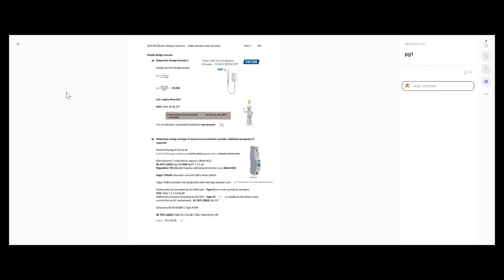So we're going to go with a 50 amp Type B for the MCB side of the RCBO, and a Type AC for the RCD part — 30 milliamps. We'll select a BS EN 61009-1, which is the product standard for an RCBO, Type B 50 amp. When we look back at the formula, I need a protective device equal to or greater than my design current. I couldn't choose a 45 amp RCBO because it's less than the design current, so the next size up is 50 amp. Table 41.3 of the regs on page 68 or Table B6 of the on-site guide lists all the different ratings of our RCBOs and MCBs. We've got a 45.65 amp design current and a 50 amp protective device.